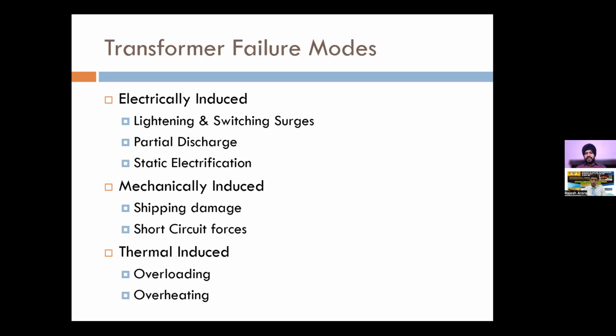And then overheating can also be an issue. Overheating is slightly different from overloading. It is possible that the transformer design is improper or the cooling system is not proper. Then in those cases, there may be some hotspots which get formed inside the transformer, causing local hotspots and damage to the insulation. So these can in turn cause thermally induced overheating, which would ultimately lead to the failure of the insulation and ultimately failure of the transformer.